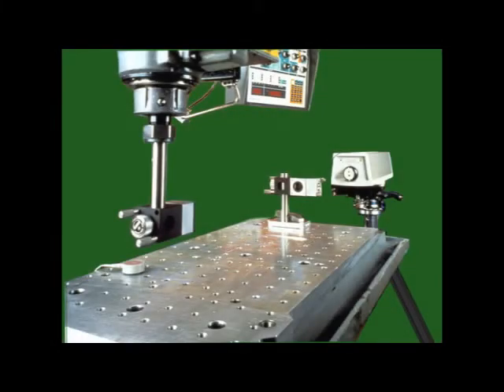Here is an illustration of the traditional interferometer laser most folks are familiar with. You have the laser on the tripod, the alignment to an external interferometer, and then another alignment to the target retroreflector. This setup requires a three-point alignment and it can be extremely difficult to set up due to access and placement of all the interferometer components.